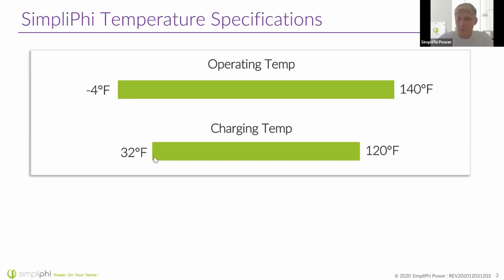The low end is going to be where you might run into issues, whereas on the high end, it's very rare to run into issues charging or discharging. Part of the reason for this is our use of lithium iron phosphate chemistry, which is inherently safer and more thermally stable compared to a lot of cobalt-based batteries. Cobalt-based batteries just cannot safely reach this type of temperature when charging, or you risk getting close to a thermal runaway event.